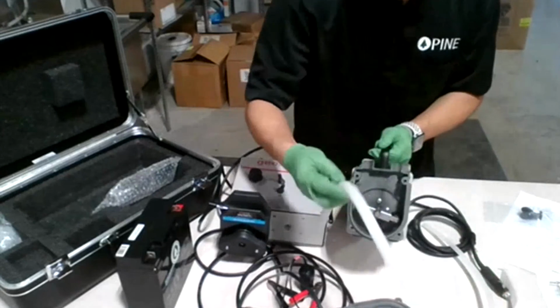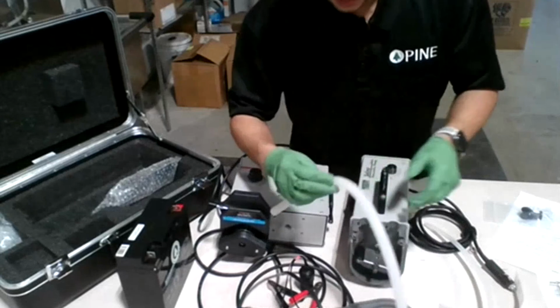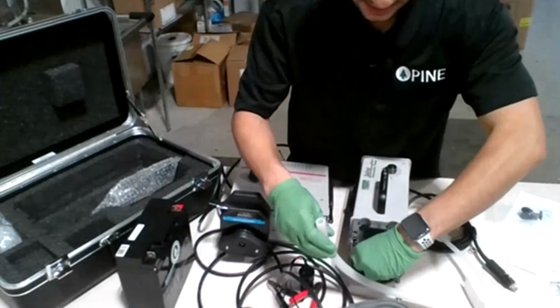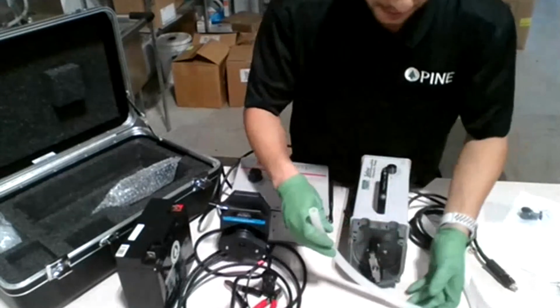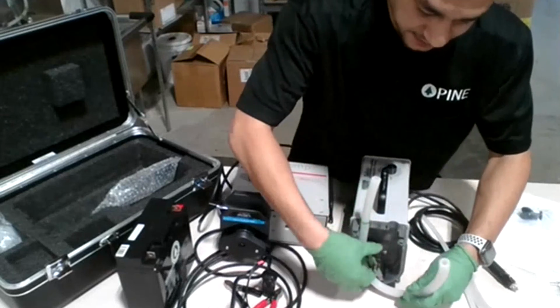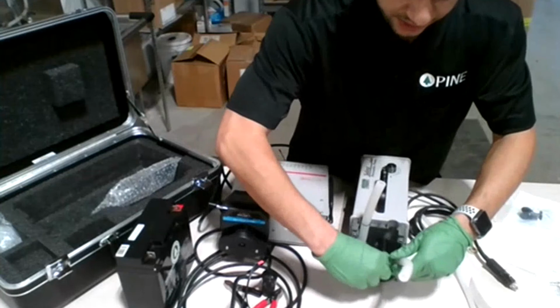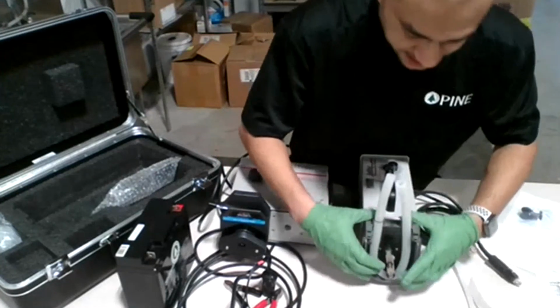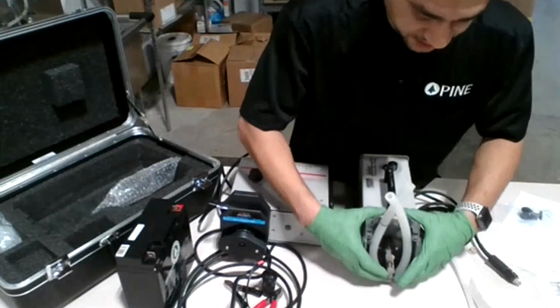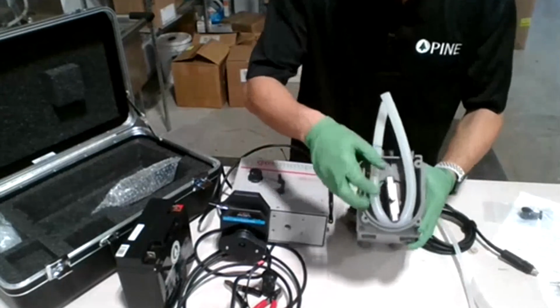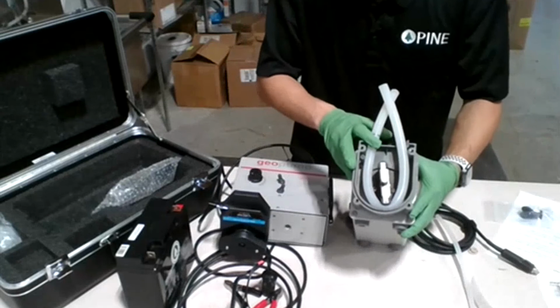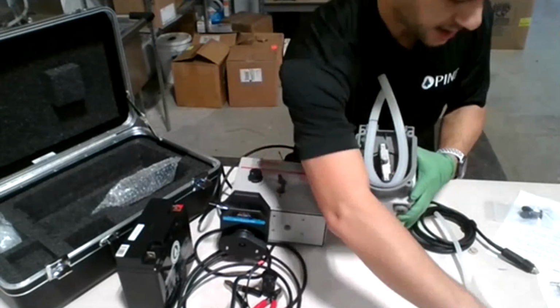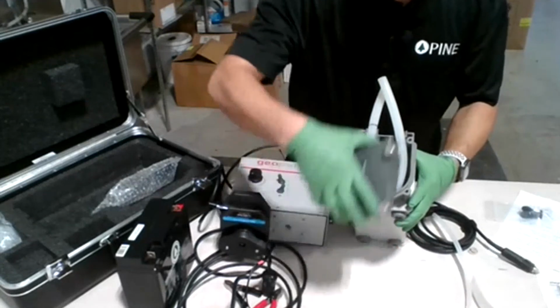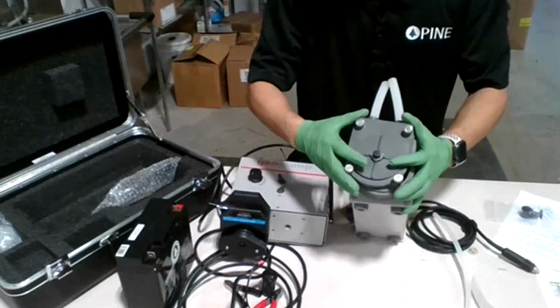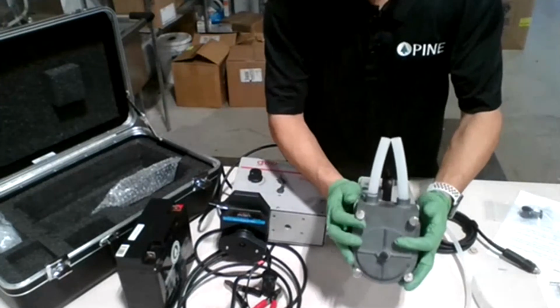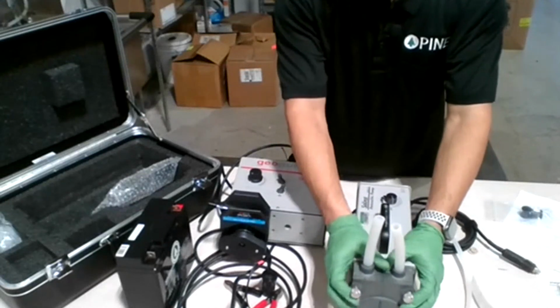For the 5/8 tubing, you simply insert the tubing this way on one side, then with your hand rotate the shaft until the other side is properly seated inside. To make sure the tubing is seated properly, there are two rollers here so the tubing won't get stuck while operating. Once you've done that, you can put the cover back this way, just like so, and now you can start your sampling.